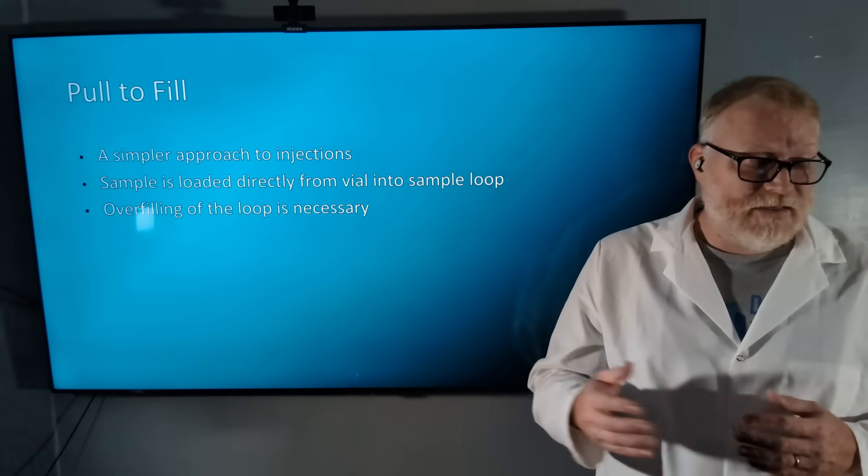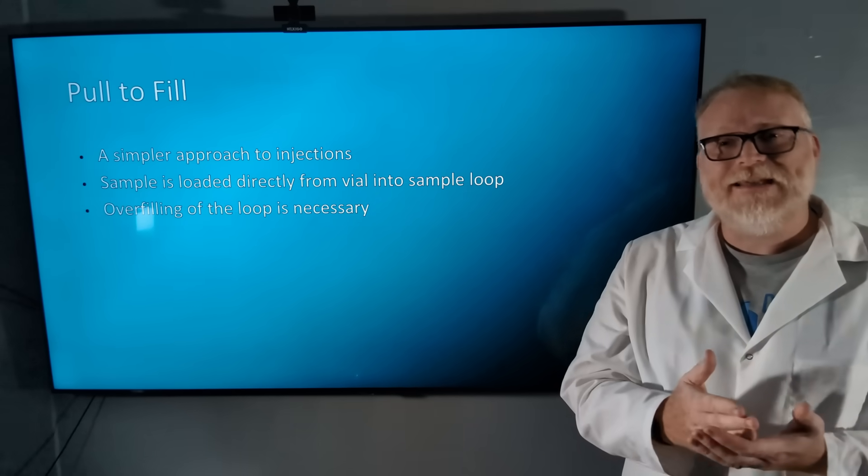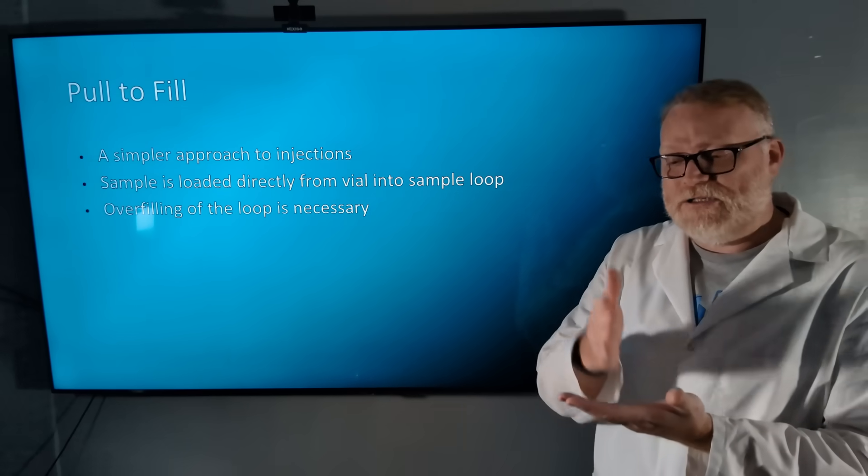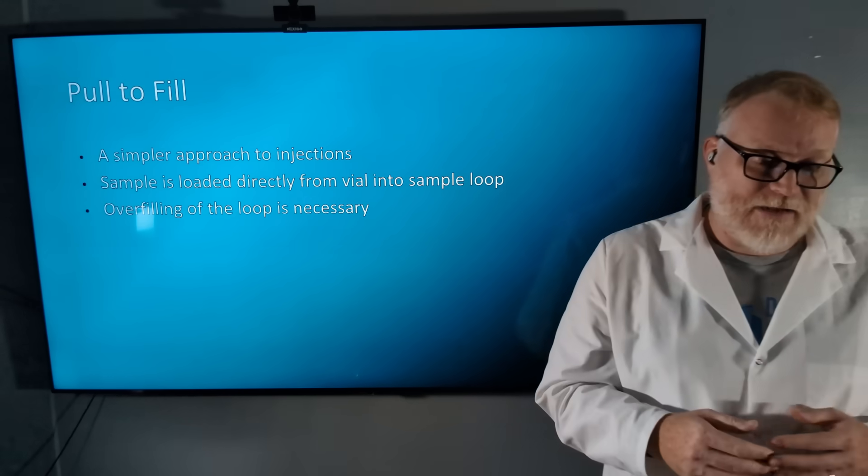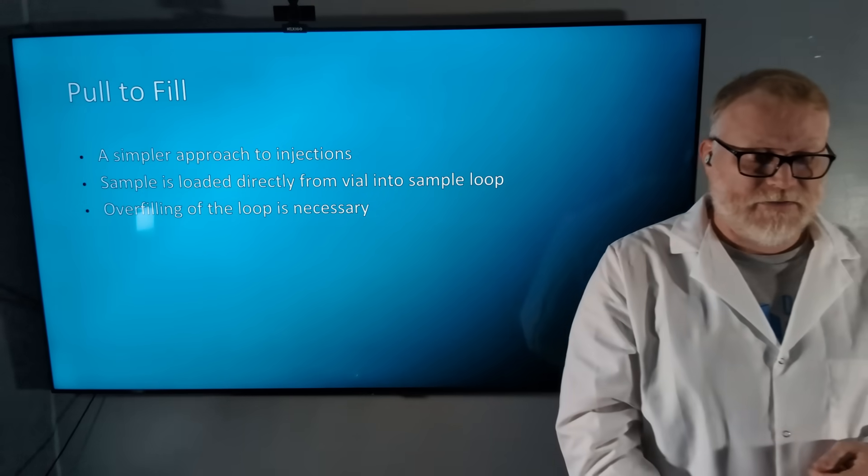Overfilling of the loop is necessary because that gives us a very consistent injection. From sample-to-sample, we know that we're injecting the same amount every single time with no variability. No variability leads to more repeatable results.